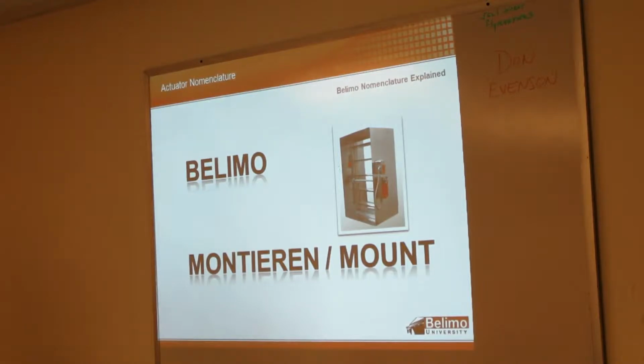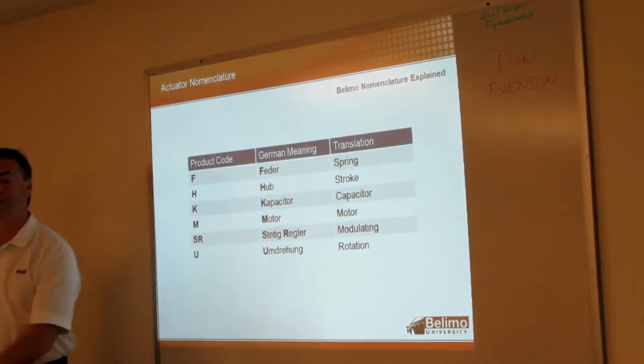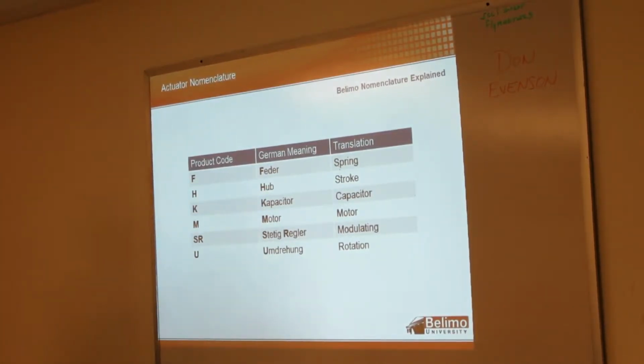Because we're a Swiss-German company, and you see the different German words here, that's why dash SR does not mean spring return. So, that first one, the LF24-MFT, that was the spring return model, because there's a word Feder in German, which means spring. So that F in the second spot in the part number, if you see an F in a Belimo actuator, that means it's a spring return actuator.